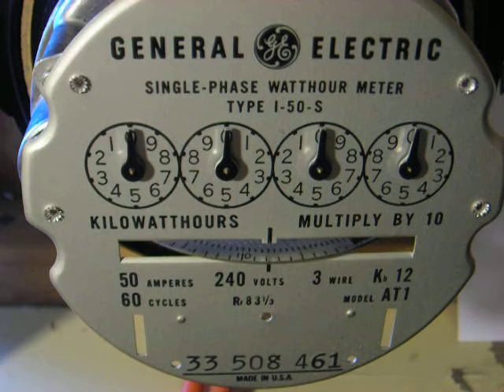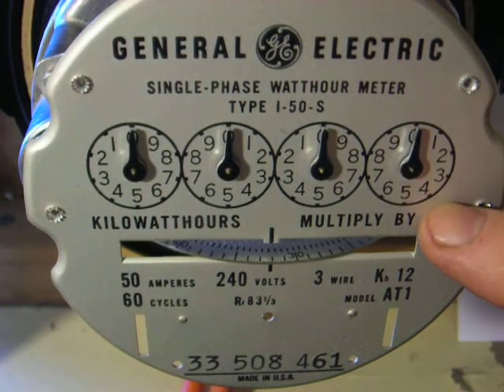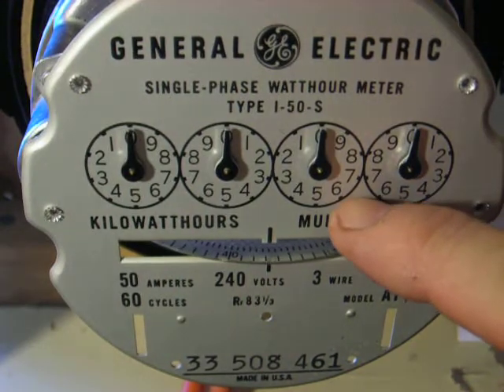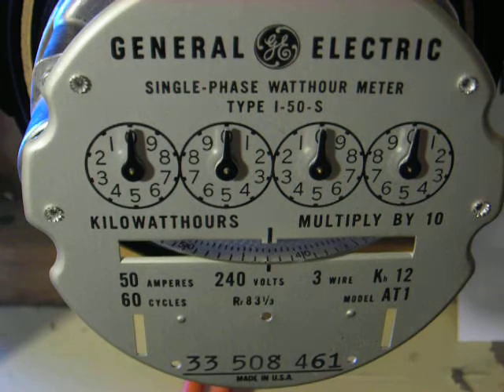This is the I-50S single phase watt meter in a configuration that has a multiplier by 10, such that on this first digit, instead of being 1 kilowatt hour, this would be 10 kilowatt hours. This 4 on here would mean 40 kilowatt hours. If this is on the 6, instead of being 6 it would be 60 kilowatt hours. They did that to register a consumer that had a lot of current, before they had meters that had 5 dials on them.